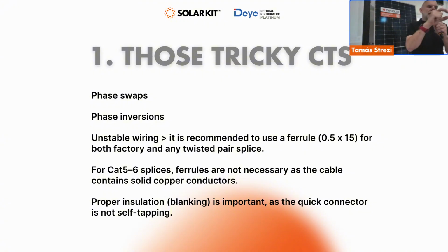So using a small but longer type of ferrule helps a lot to make a proper secure connection. And since the CTs are kind of the error signal of a highly complex inverter circuit, getting a wrong error signal makes the inverter go really crazy. I've seen inverters running, feeding in one phase and producing energy on the other phase and running for months in circles at a really high temperature. Which is also one of my key tools to detect these kind of problems, is checking the inverter temperature.